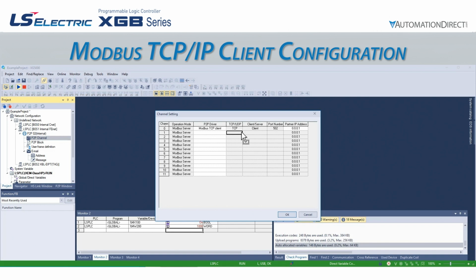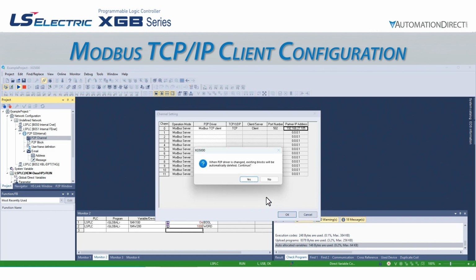Once we have set channel 0 as Modbus TCP client, it will auto-populate the TCP, UDP, client server, and port number fields. We can then set the IP address of the Modbus server we wish to communicate with. In our example, we are going to control a GS20 variable frequency drive located at 192.168.27.105. We can then select OK to confirm our settings.